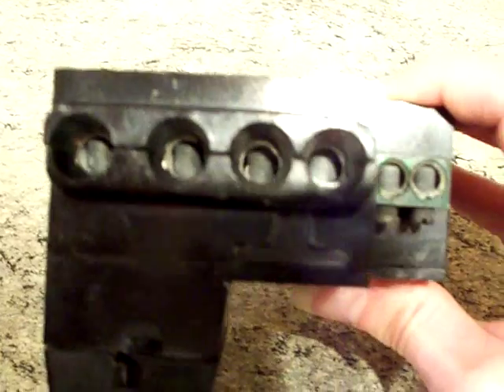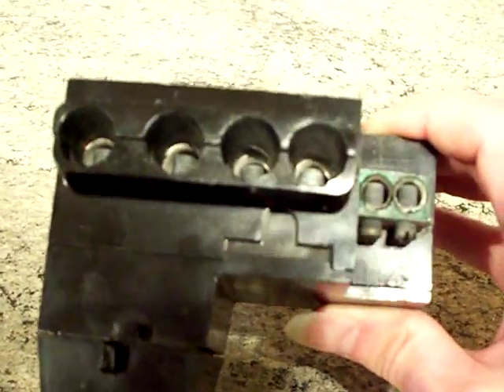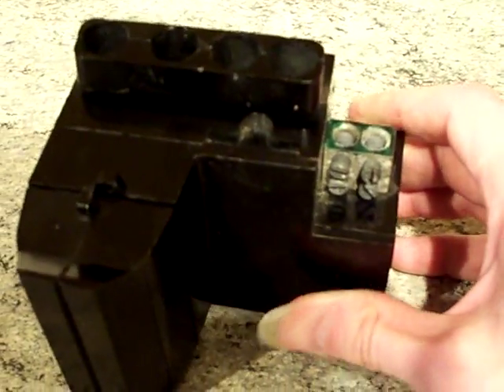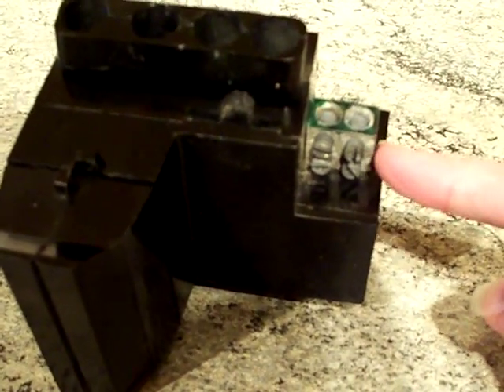They are quite sizeable holes. I think you can probably get 25mm cables in there, or quite possibly 35mm — I'm unsure though. I've put 25mm cables in there and they fit in quite snug, so I don't know whether the 35s would go in, but there are your earth terminals.